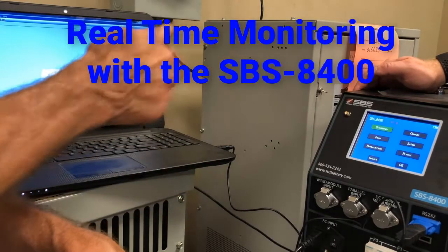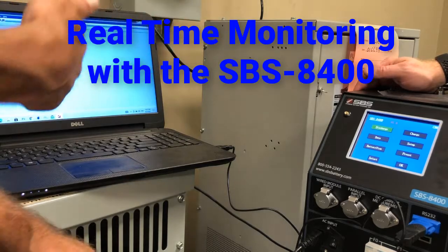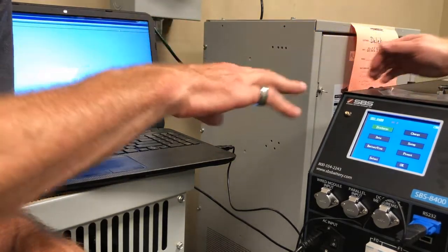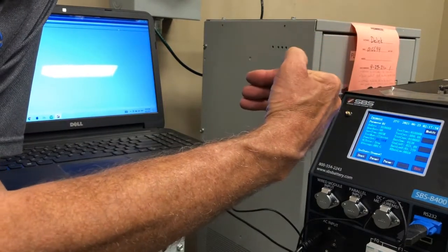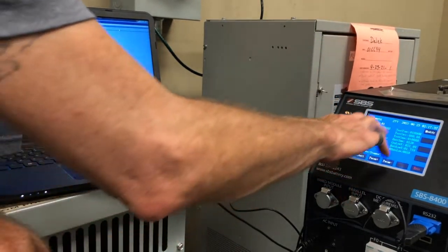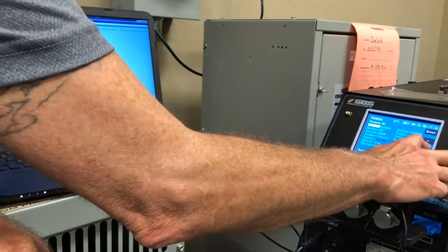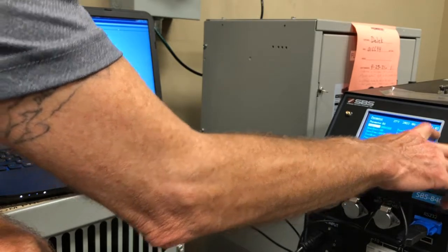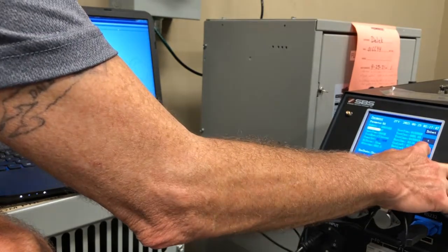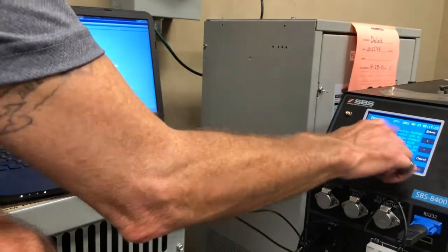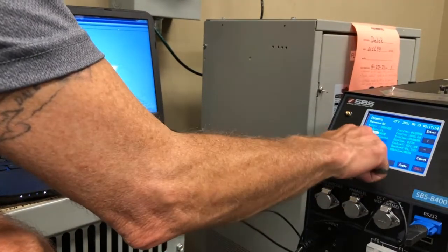So in order to set up the load bank to do real-time monitoring, the first thing that I've got to do is set my parameters on the load bank of what the test is going to run. Okay. So we know from preset one on the other load bank, we're going to modify this to 95 amp hours, 1 hour rate, 5-minute save time, constant current, one group, one string.